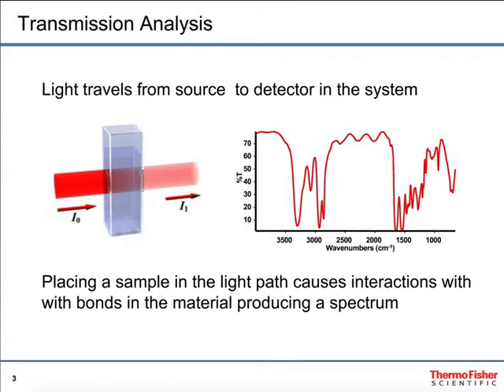Transmission is probably the classic method. In this case, the IR beam passes through the sample compartment. We record a background, then we introduce a sample into that beam. The sample absorbs some percentage of that beam. The resulting light that goes to the detector is then ratioed to the initial light. That ratio provides something called a percent T, or transmission spectrum.